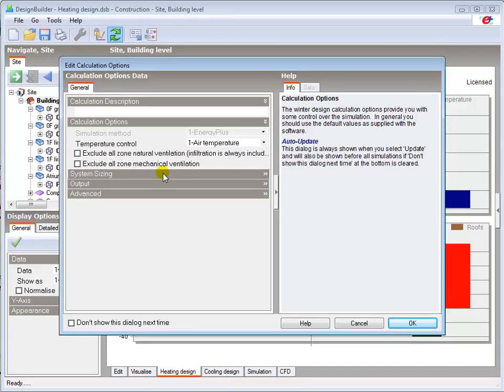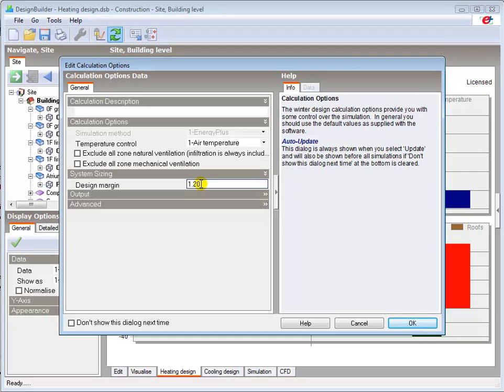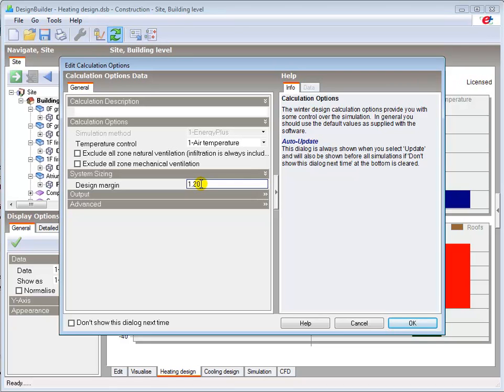The design margin is set to 1.2 by default which means our plant sizes will be based on the calculated heat loss plus 20% to cater for any additional heating capacity required when the heating system has been switched off for extended periods, for example overnight or over the weekend. It effectively reduces the preheat time required to achieve comfort set points at design winter conditions. The design margin can be increased or decreased if desired based on the system design, but note that some national energy codes penalise excessive design margins.